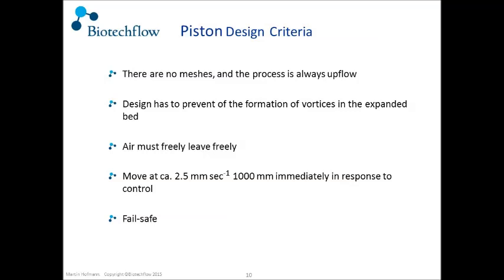The next challenge was the piston. In this column, at this diameter, it was for pilot study and phase 3 production. We used a piston to find out what bed height we needed. There are no meshes and the process is always upflow. If the column with a stirrer got a vortex, the tungsten carbide media left the column and went straight out of the top, sticking to all the pipework in the GE skid. To stop the formation of a vortex, air must leave freely and the piston must move 1 metre at 2.5 millimetres per second. Fail-safe is a system of relief valves.